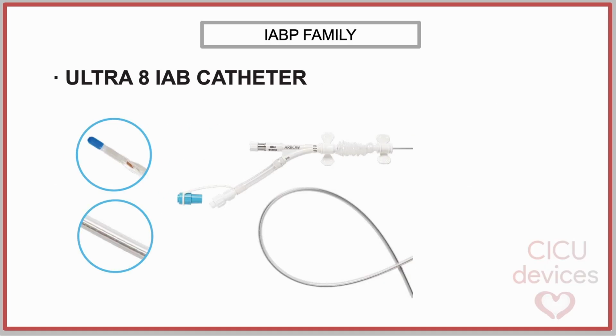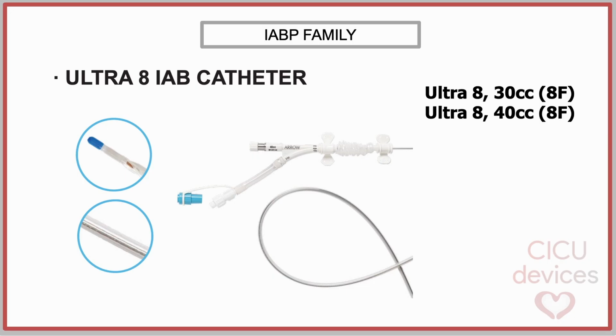The Ultra 8 is an 8 French intra-aortic balloon catheter designed to provide an optimal balance between deliverability and mechanical performance. It is available in 2 balloon volumes, a 30 milliliters model recommended for patients shorter than 162 centimeters, and a 40 milliliters model intended for patients between 162 and 182 centimeters, according to Teleflex sizing recommendations. A large central lumen enables fluid-filled arterial pressure monitoring, providing a high-fidelity aortic pressure waveform while minimizing the risk of lumen clotting.